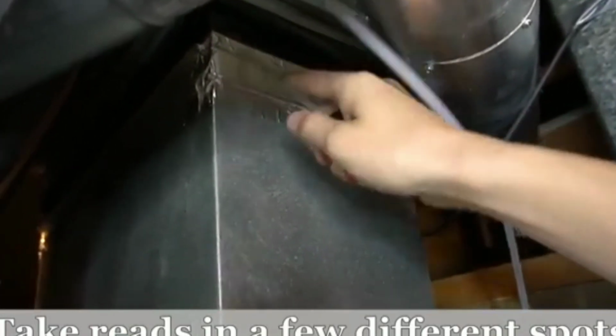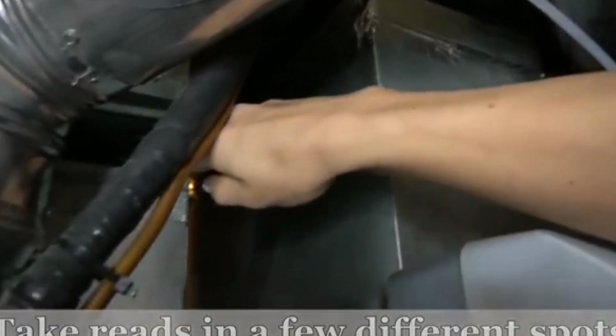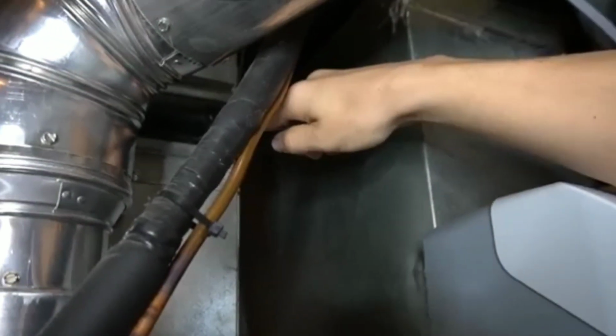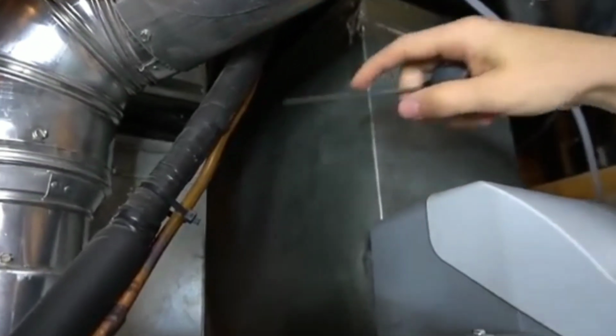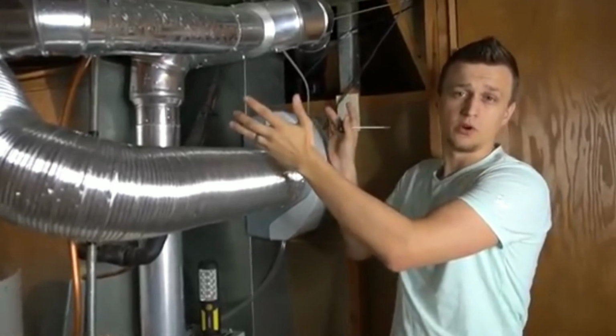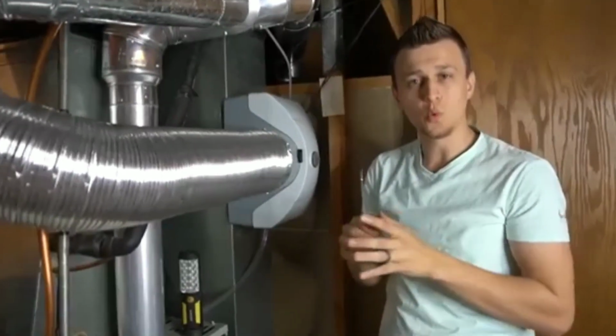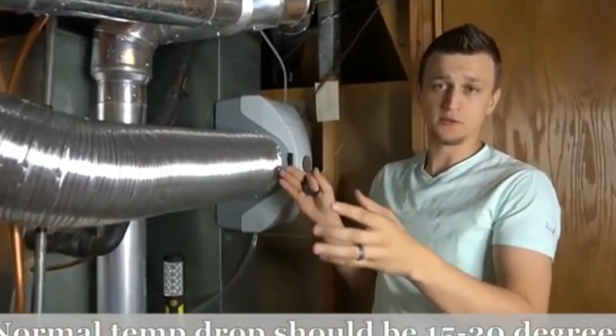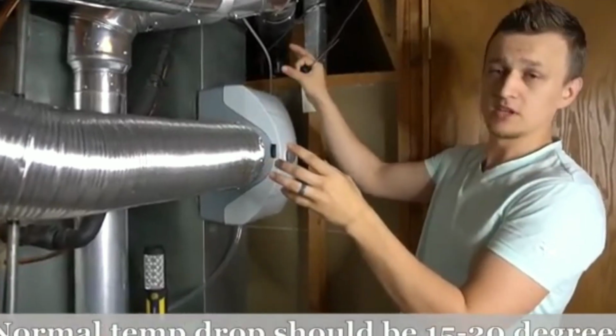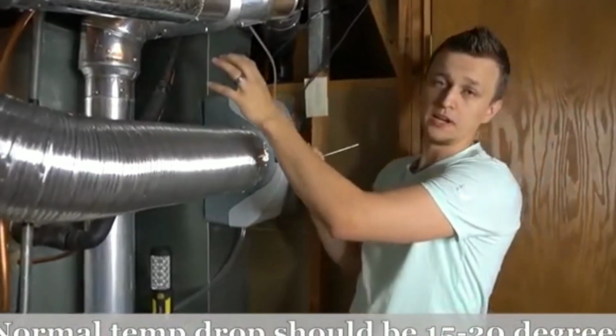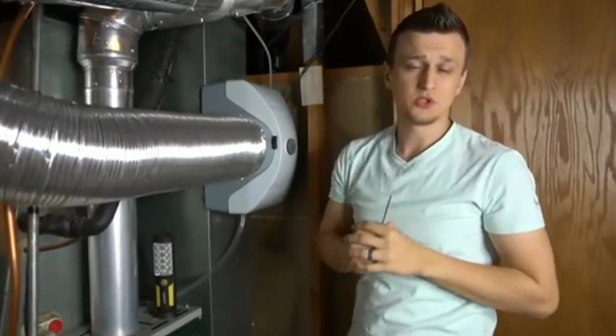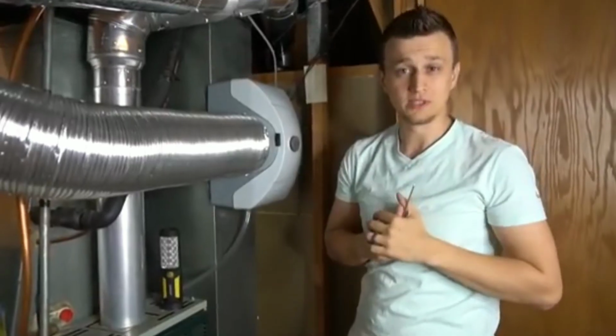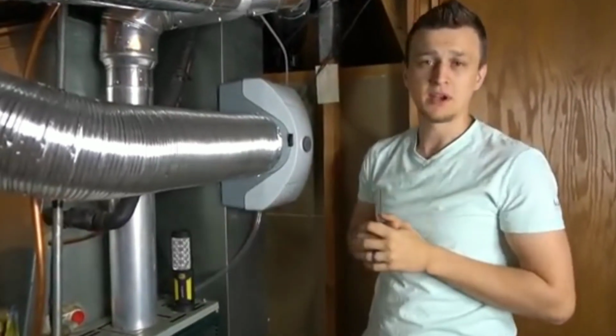Take a temperature reading here, and then take a temperature reading in the supply while the unit is running, after you let it run for 5-10 minutes. And what you're looking for there is a 15 to 20 degree temperature difference between your return air temperature and the supply air temperature. I live in Minnesota and it's actually 45 degrees outside right now, so I'm not going to turn on my air conditioner.